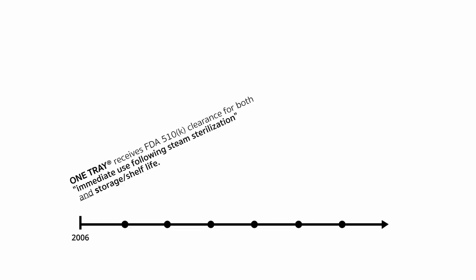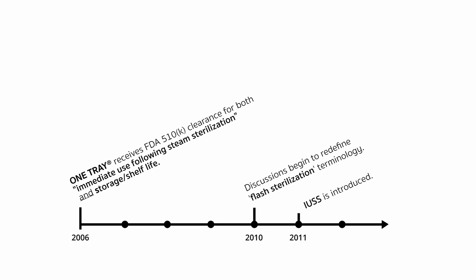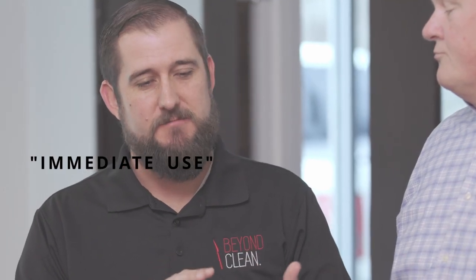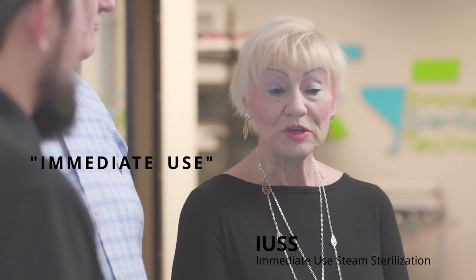However, we go full force into the future. Since we're back in 2005, 2006, we didn't start meeting at a table until 2010, with the paper being published in 2011. So the terminology is completely different. The similarity between the terms immediate use from the one tray FDA clearance document and immediate use steam sterilization, or IUSS, has led many people to believe they mean the same thing, something IST has worked hard to correct within the industry. So we've always had shelf life since the 510K was cleared, and so for that reason, you can store our tray.